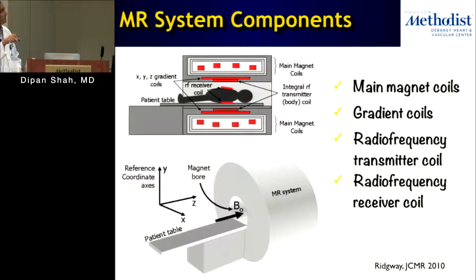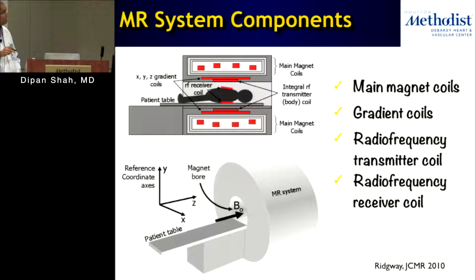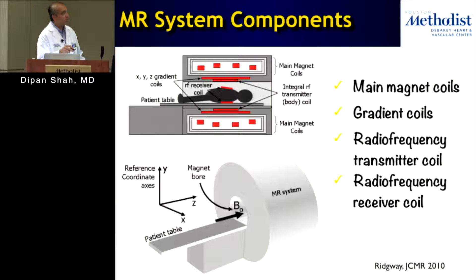Inside the scanner itself you have the table that moves in and out, the main magnetic coils which produce the main magnetic field, a set of XYZ gradient coils that cause a slight alteration to the magnetic field, and an integrated RF transmitter which transmits radio frequency energy. So we have: main magnetic coils, gradient coils, RF transmitter coil, and radio frequency receiver coils.